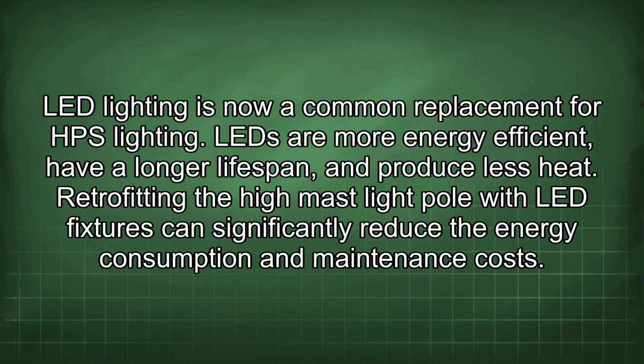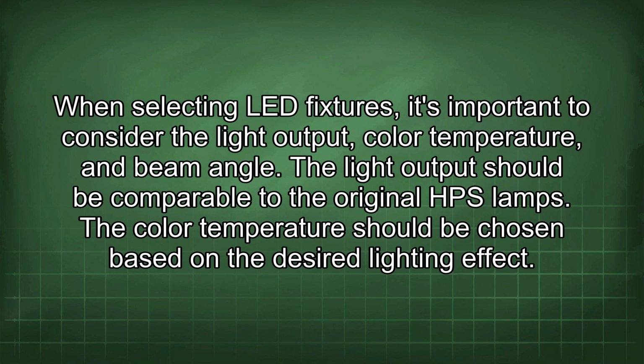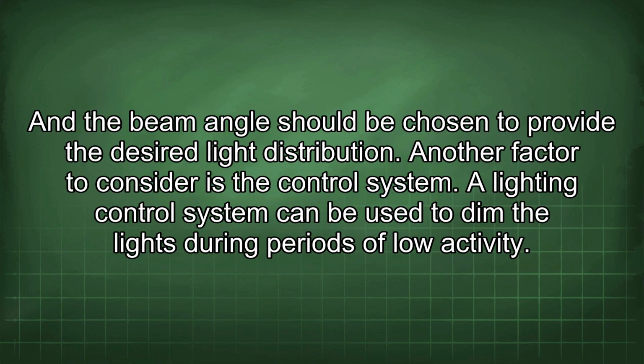LED are more energy efficient, have a longer lifespan, and produce less heat. Retrofitting the high mast light pole with LED fixtures can significantly reduce the energy consumption and maintenance costs. When selecting LED fixtures, it's important to consider the light output, color temperature, and beam angle. The light output should be comparable to the original HPS lamps. The color temperature should be chosen based on the desired lighting effect, and the beam angle should be chosen to provide the desired light distribution.